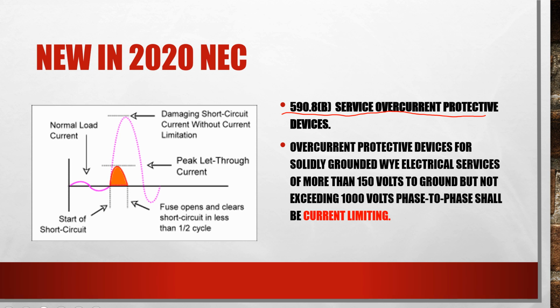Now, what that's telling us is, if we look right here at our picture of our sine wave, right here is our normal condition. This is our current waveform that we're looking at, and we're using some current. We have a nice steady value of our sine wave. But whenever we have a fault condition, a short circuit or a ground fault right here, then look at how the value went up. Pow, way up here, meaning we have a tremendous amount of current flowing at this time. And so, left to continue, this is going to cause great damage to the equipment. It could cause harm to anyone around. It could start a fire. There could be many things come from this tremendous amount of current that would flow during this fault condition.